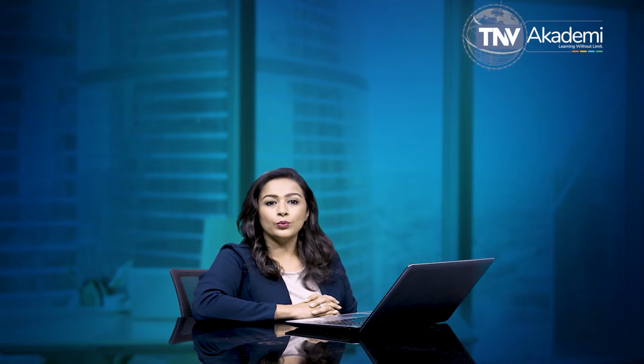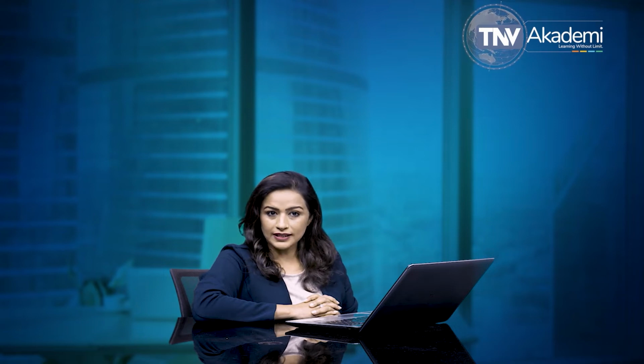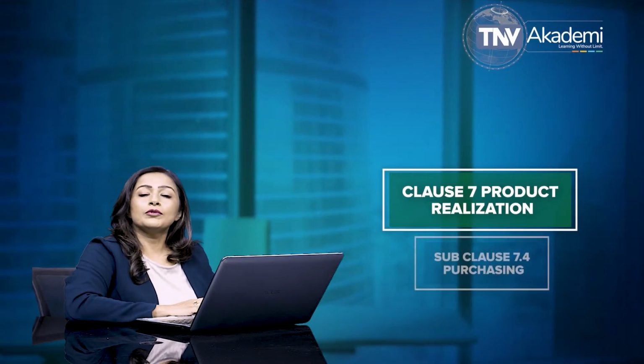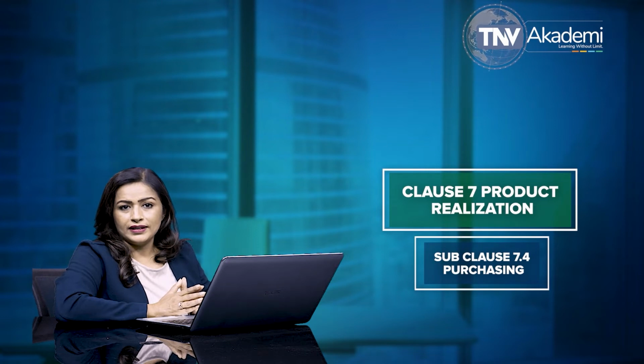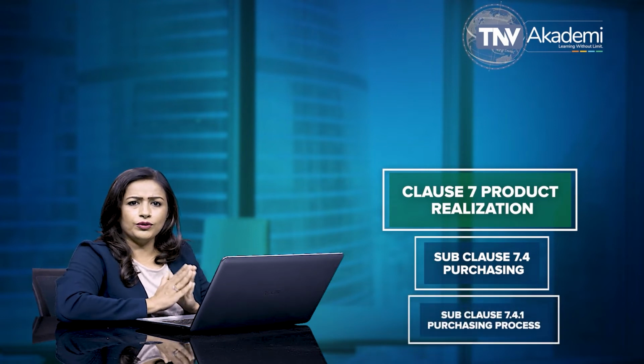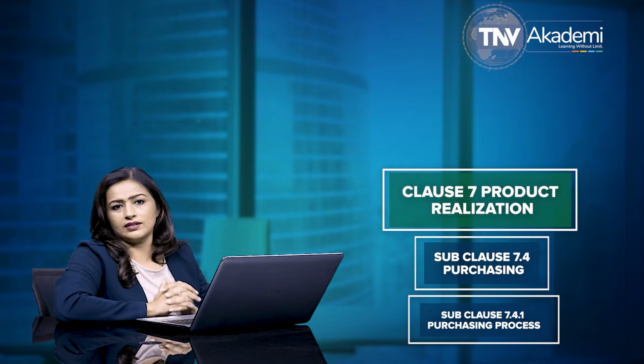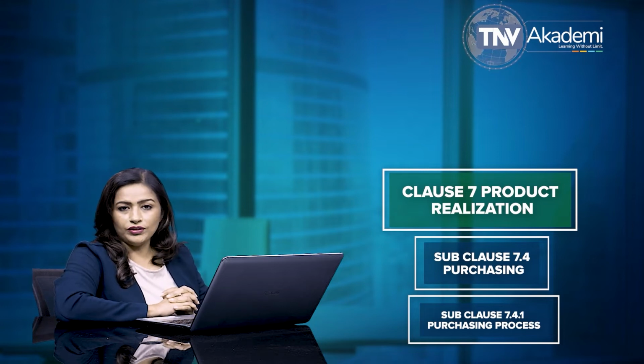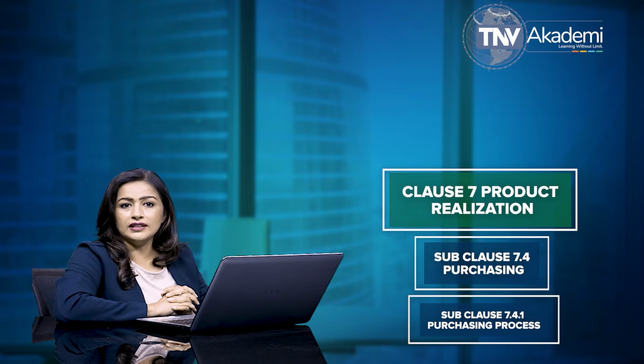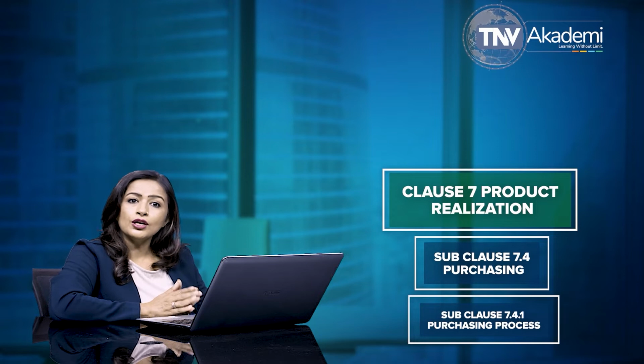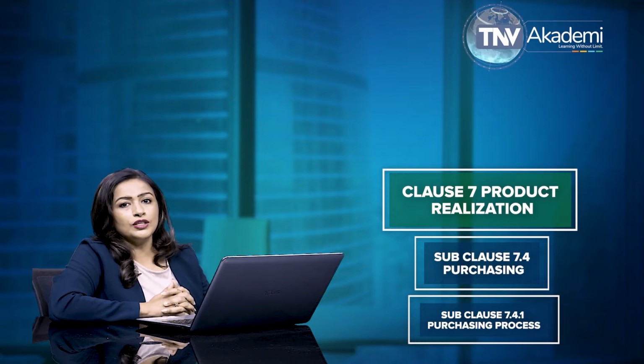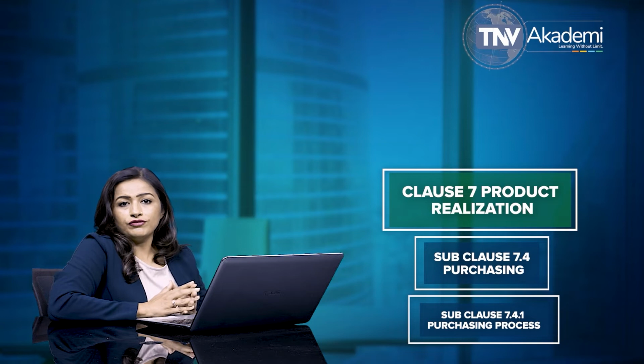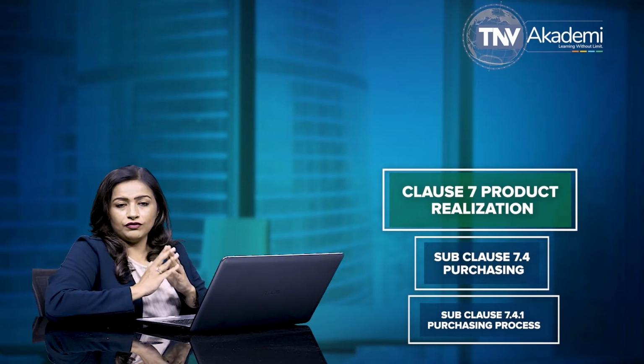In this session, we are going to talk about an international standard ISO 13485:2016. Let's discuss subclause 7.4 purchasing. Let me talk about the subclause 7.4.1 purchasing process. This subclause 7.4.1 of ISO 13485 states that the organization is required to document procedures to ensure that purchased product conforms to specified purchasing information.